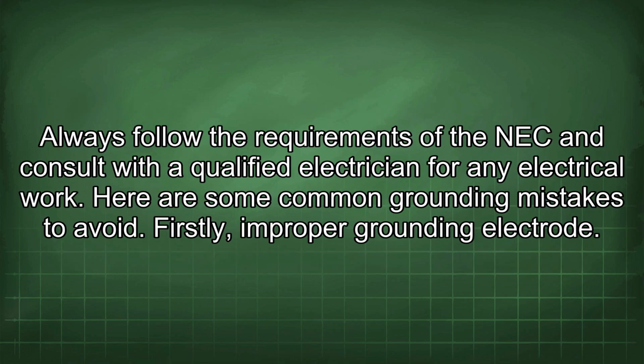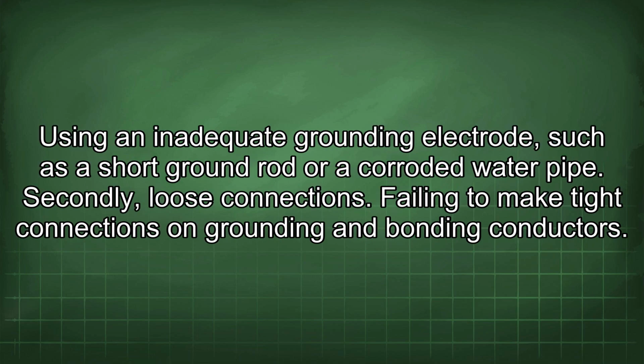Always follow the requirements of the NEC and consult with a qualified electrician for any electrical work. Here are some common grounding mistakes to avoid. Firstly, improper grounding electrode. Using an inadequate grounding electrode, such as a short ground rod or a corroded water pipe. Secondly, loose connections. Failing to make tight connections on grounding and bonding conductors.